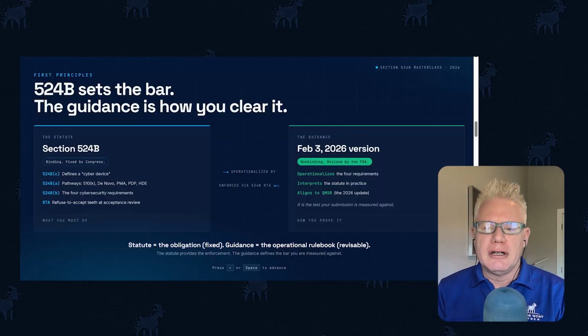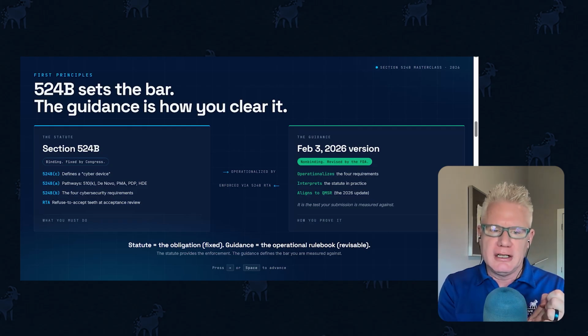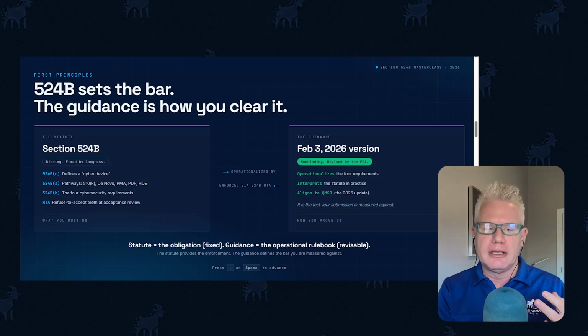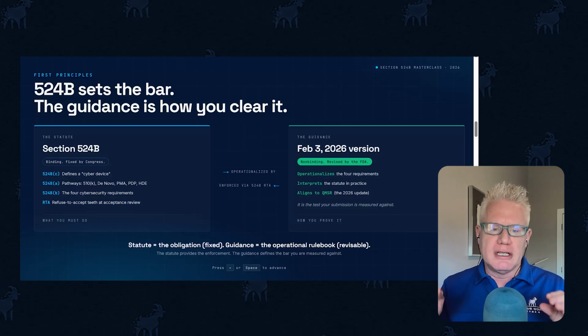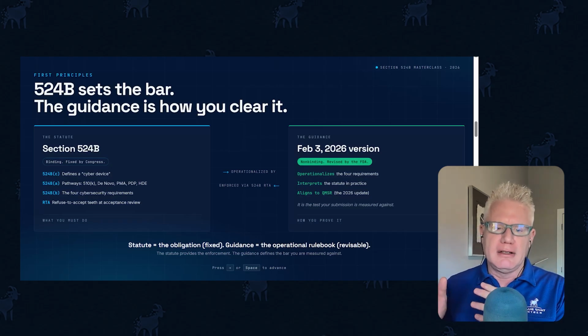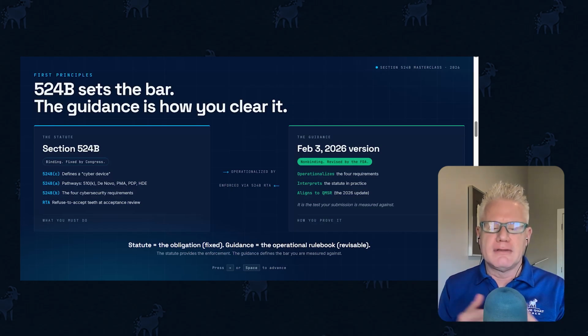This is a good analogy that shows how the two tie together. So the statute or the law is section 524B. It is broken down into various components. Section C defines a cyber device, which is anything with software and a way to connect to it. And we'll go into a little more detail of that in a second. 524B Section A defines the pathways, the 510K, de novo, PMA, PDP, HDE. These are the applicable pathways that 524B applies to. And then 524B Section B defines the 4 cybersecurity requirements. And we'll go into those in a second as well.